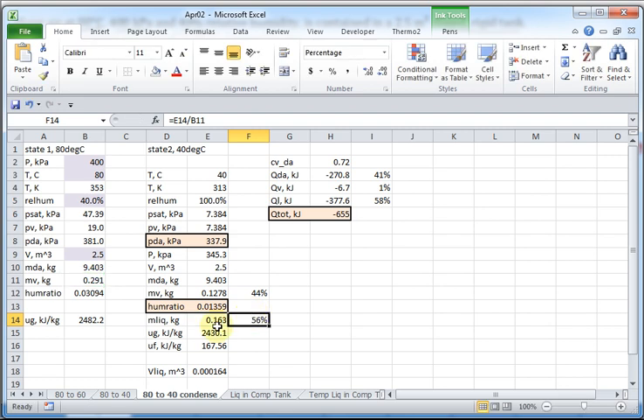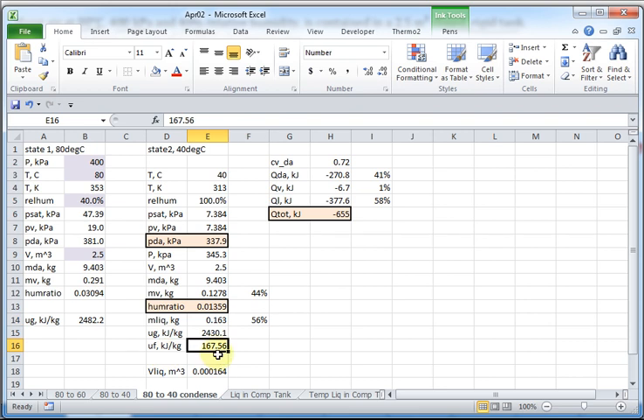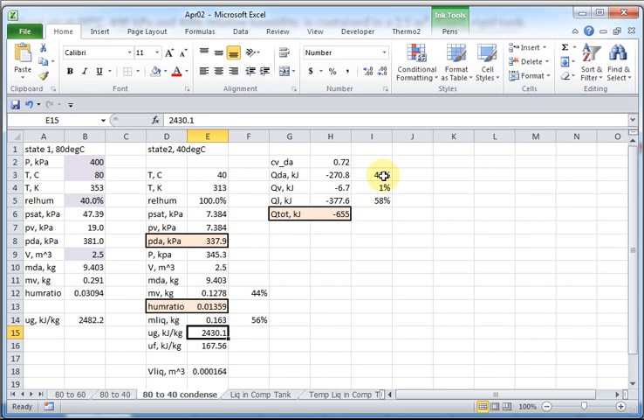So, quite a bit of the water has condensed. And you have to look up uf for that temperature of 40 degrees C, ug for that temperature. And when you calculate the total amount of cooling required, it's a lot higher, 655 kilojoules. And 41 percent of it is attributed to cooling the air, cooling the vapor that stays in the vapor state, only 1 percent. But 58 percent is associated with condensing the vapor.